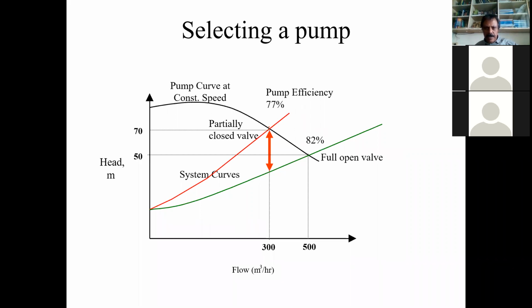And we have increased the head from 50 to 70. The pump is facing a higher head. And as per the characteristic curve, the pump delivers a lower flow rate. So whatever desired flow rate that we want, 300 meter cube, we've got it. What happens to the power? We have come from this point to this point. So at this point, the power drawn was, let us say, 55 kilowatt.